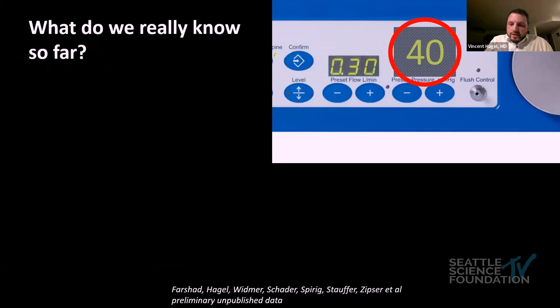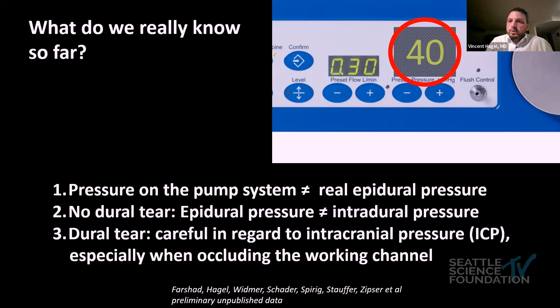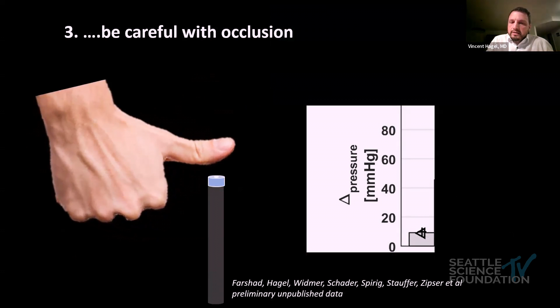So to summarize these results, what do we know so far? Obviously, the pressure that is set on the pump system does not reflect the real epidural pressure. And as long as we do not have a dural tear, the epidural pressure also does not reflect the intradural pressure. If we do have a dural tear, on the other hand, we have to be very careful with regard to the intracranial pressure, especially when we occlude the working channel in order to control bleeding. So again, just to really get the gist of that, when we occlude the working channel, even at low pressure settings, once we have a dural tear, that does significantly increase the intracranial pressure into pathological values.